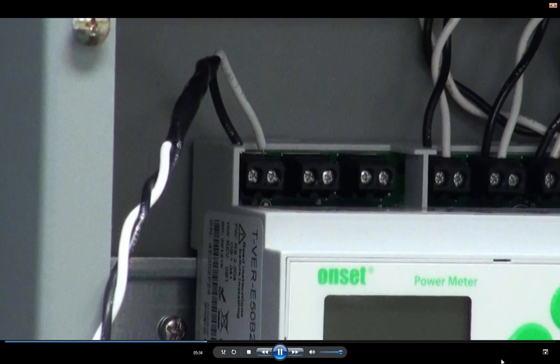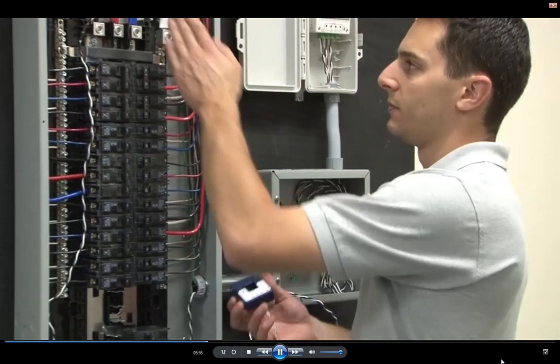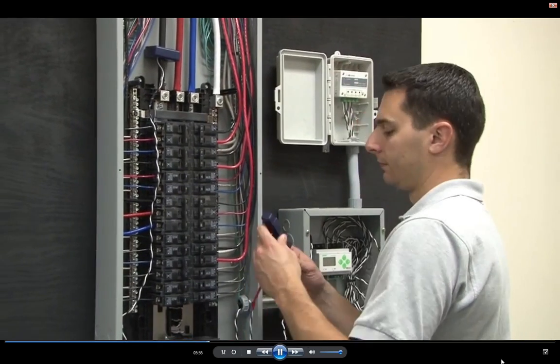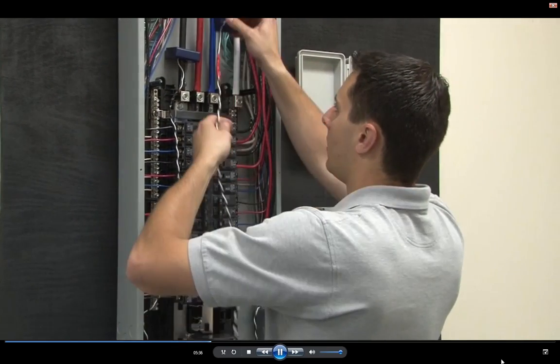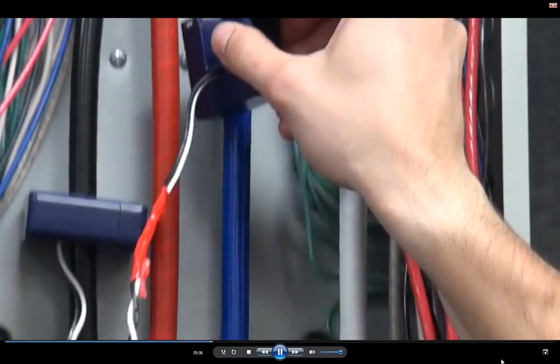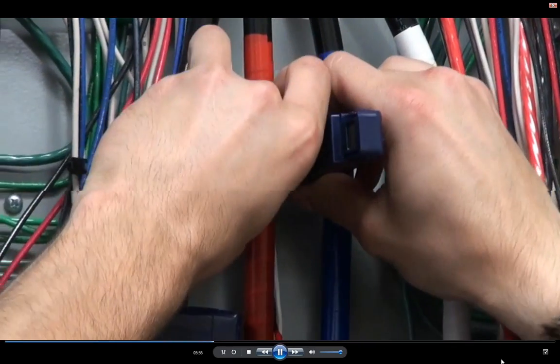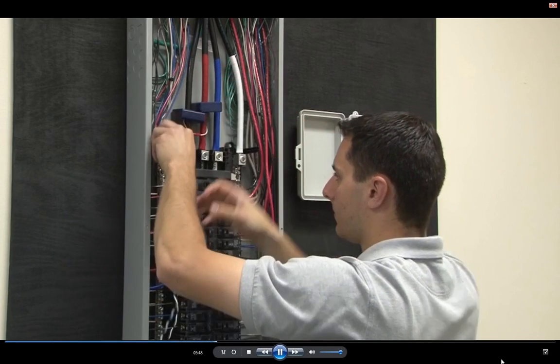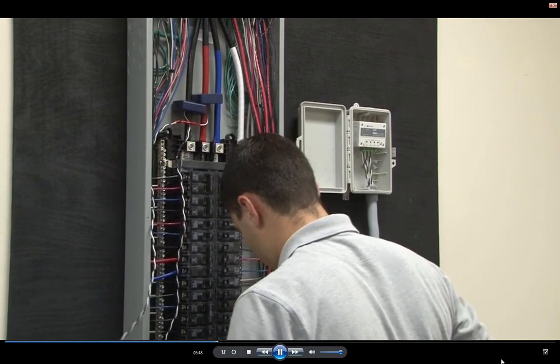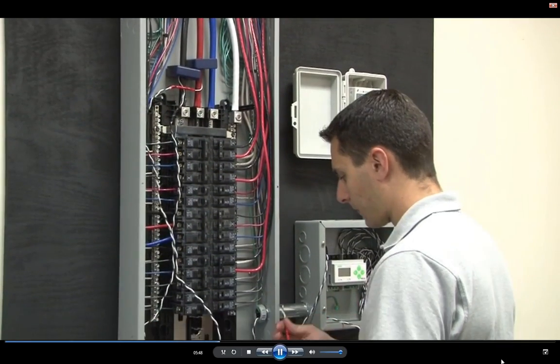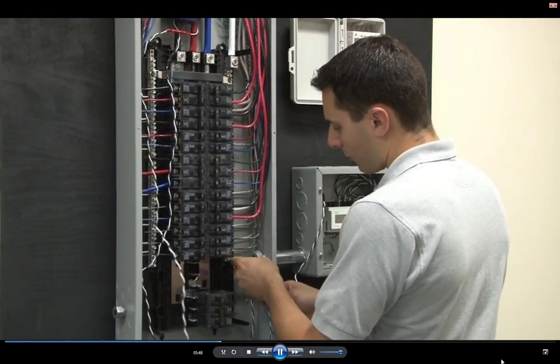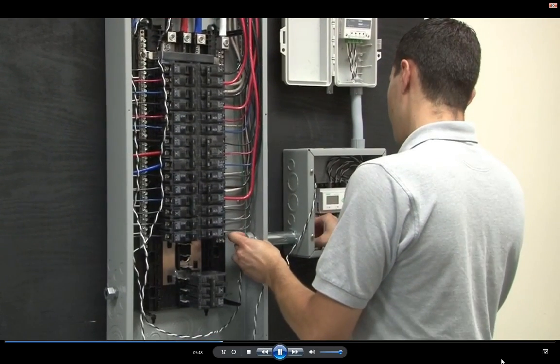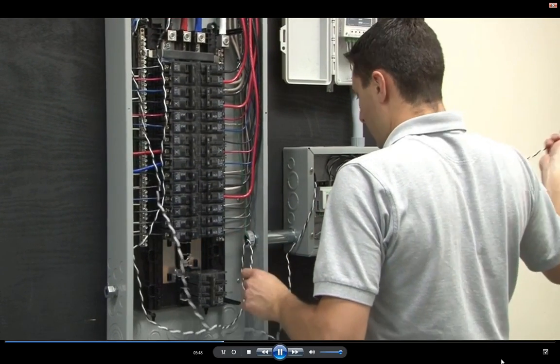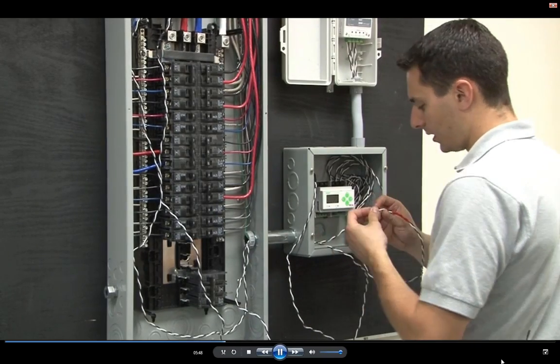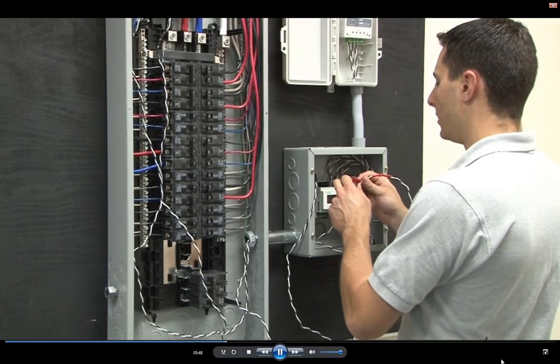We'll now connect the red phase B CT to phase B of our panel. Once again, we make sure the arrow faces the source, and we clip the CT closed. We pull the CT conductor through the conduit and connect this to the phase B CT terminal on the E50B2.